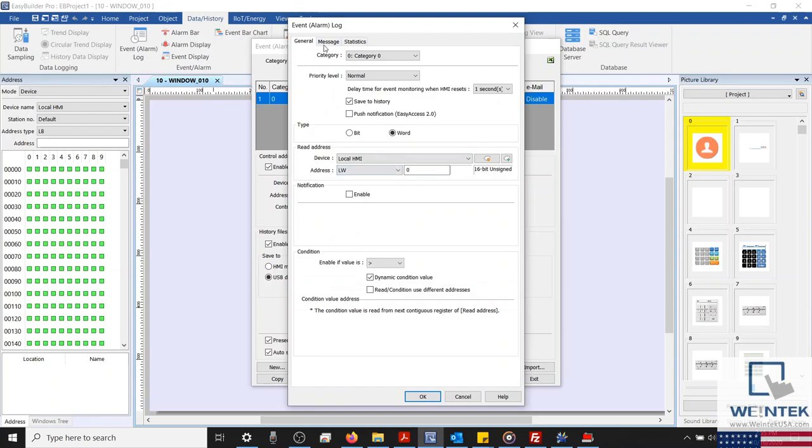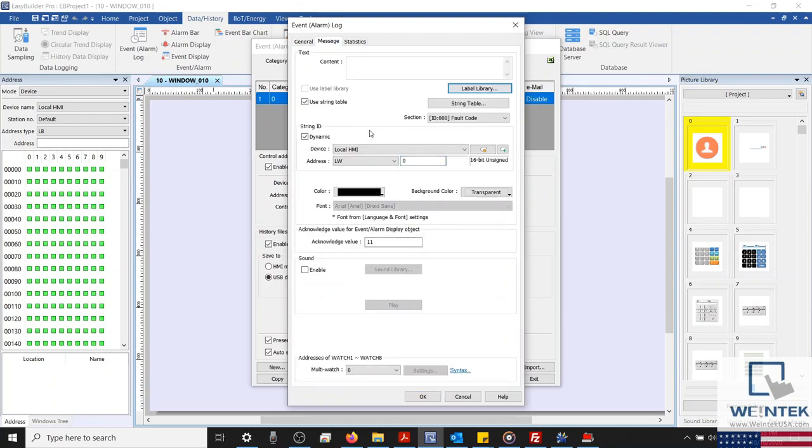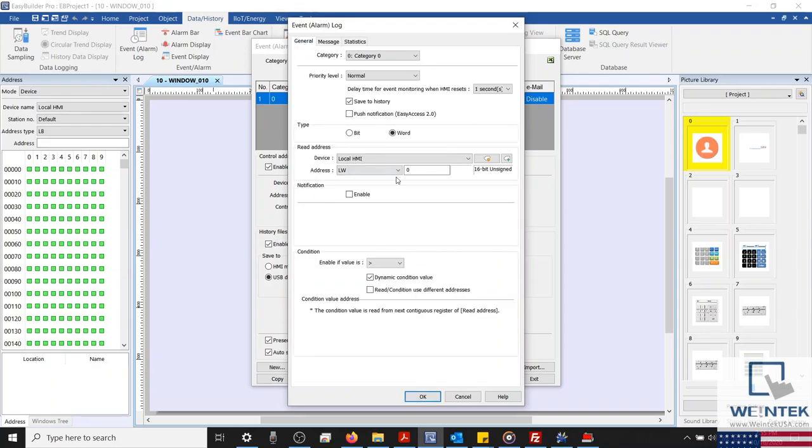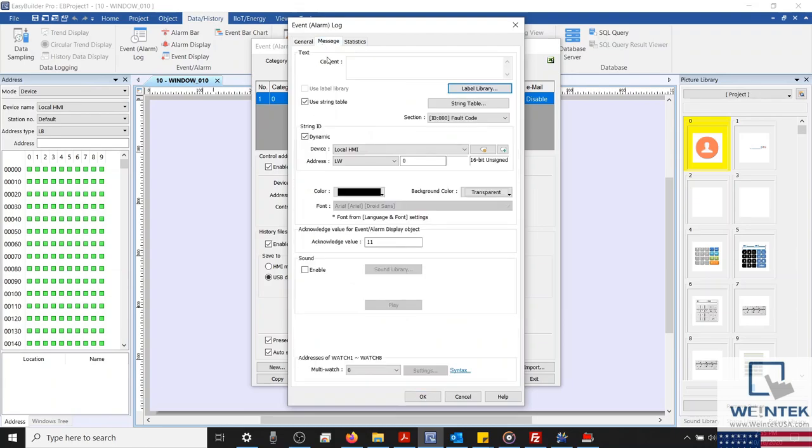So essentially, this alarm will be triggered if the read address, which is LW0, is greater than our condition value, which is specified within LW1. And the message's content will be displayed if the value within our dynamic string register corresponds with a row number within our fault code's string section. The dynamic string register is also our alarm's read address, meaning that as the alarm's value changes, the message's content will as well.